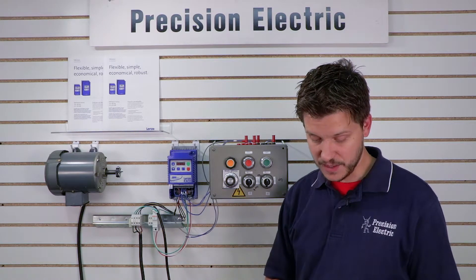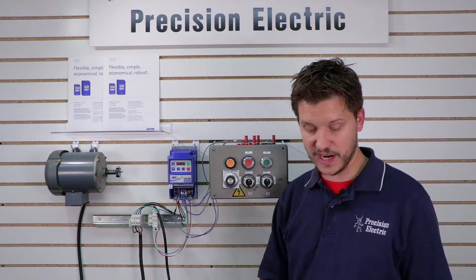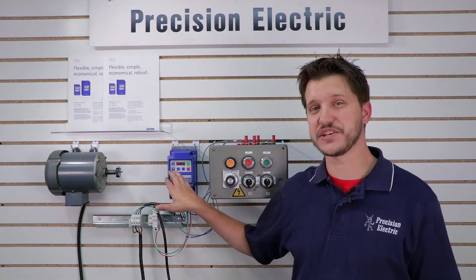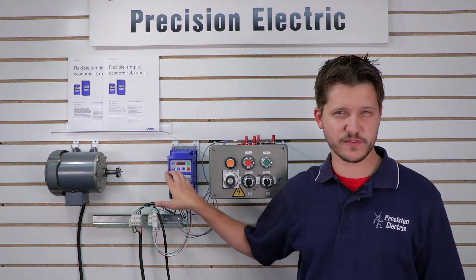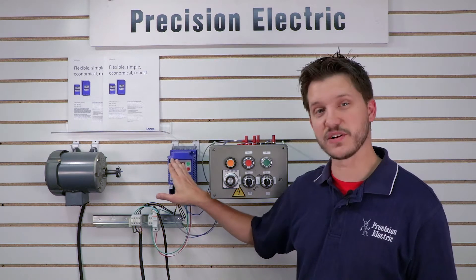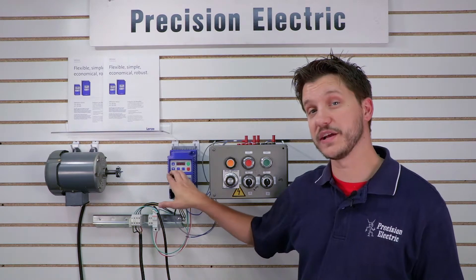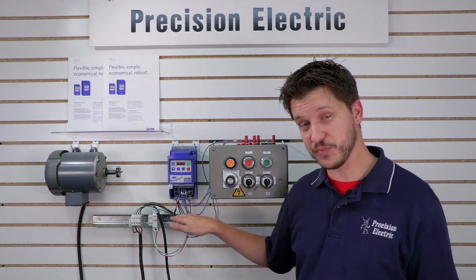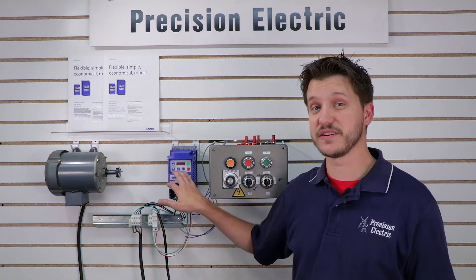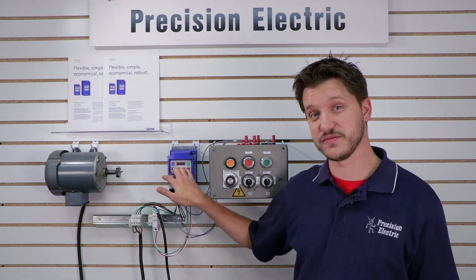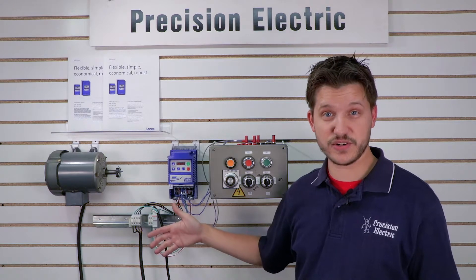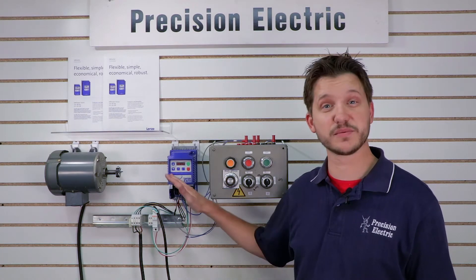The other most common fault we occur may be just a standard motor output fault or a transistor fault, which is an FOF fault. This usually occurs again in conjunction with a motor overload. So the first fault we talked about, which was the FPF. So what will happen is it's either an overload issue or it could be that your motor is shorted on the output. So you might need to get your motor tested or the third possibility is your drive output has started to fail. So you can actually get what's called an output transistor fault. So obviously the number one solution to that would be to disconnect your motor and try running your drive again. If it still gets the fault without a motor connected, then it's probably in the drive.